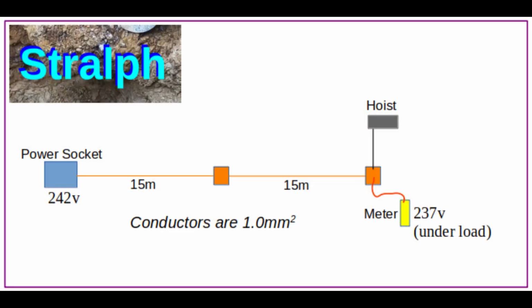Okay, this is the drawing that I did to sort of show how it's set up. The power socket on the left, the blue box, which we measured as 242 volts right before the hoist was turned on. Then the two 15 metre power cables, which I found out it's written on the side of the cable that they're 1mm squared conductors.